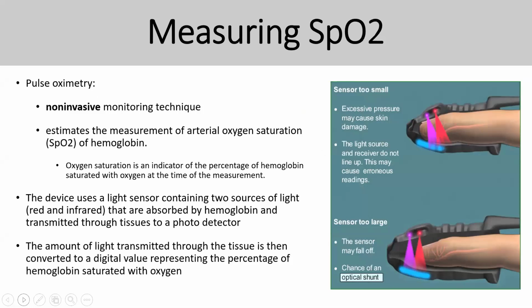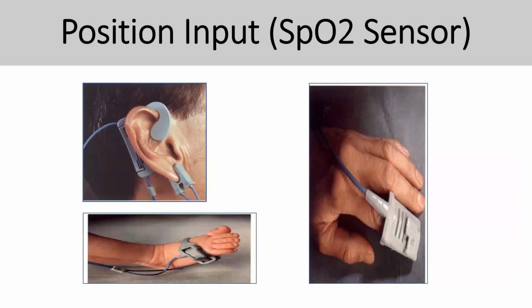So measuring SpO2 is basically a non-invasive method. They use a light sensor, with red and infrared light, and send the signal to your finger, and the light signal from there is going to rebound and be sent to the photo light sensor. So that's where it captures all the readings. So the SpO2 sensor can be placed on your ears, baby's legs, fingers. These are very common places where you can position the SpO2 sensors.